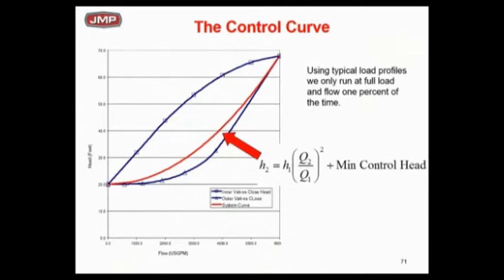You can be anywhere between those two numbers, and you have to have the pump speed to get you there, horsepower to get you there. You're beginning to see why you cannot use just one fixed control curve. You need to be able to change the differential.